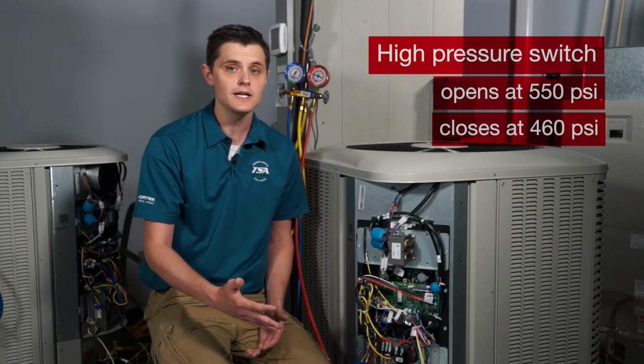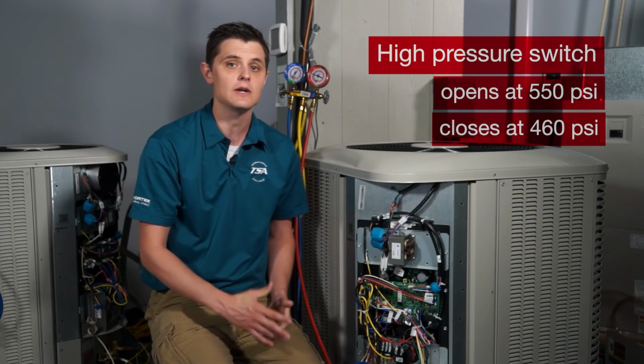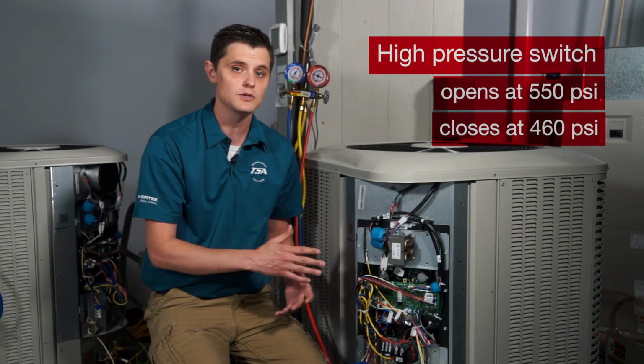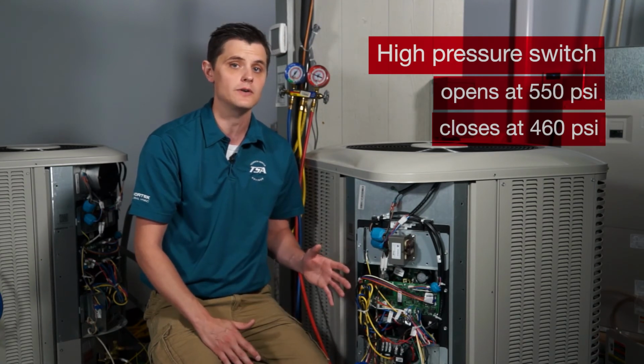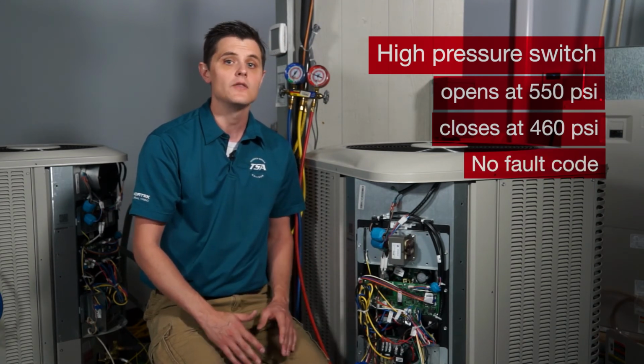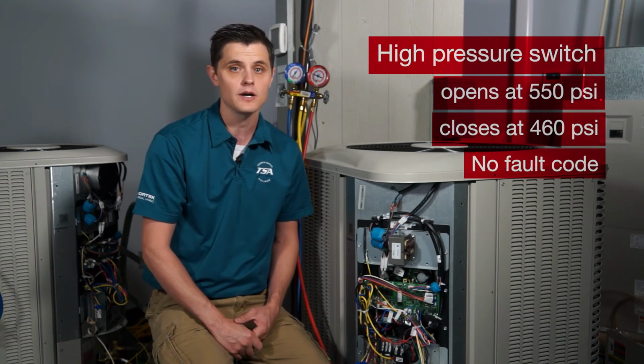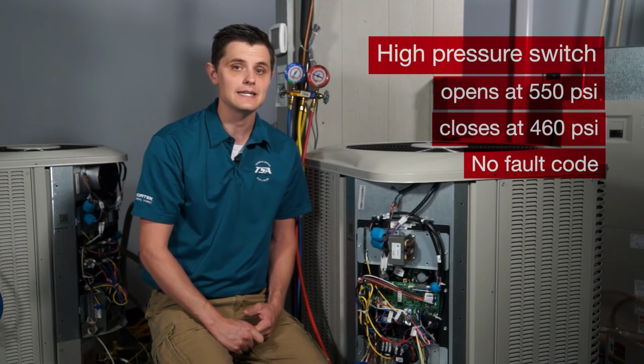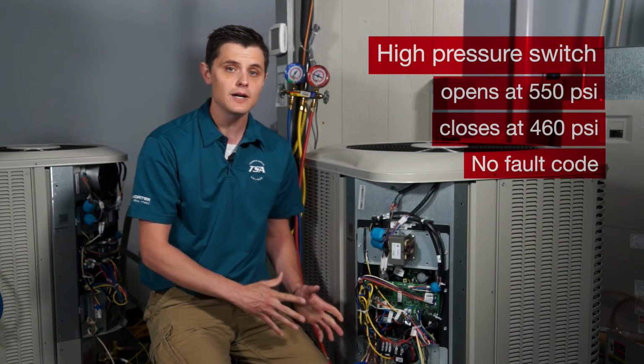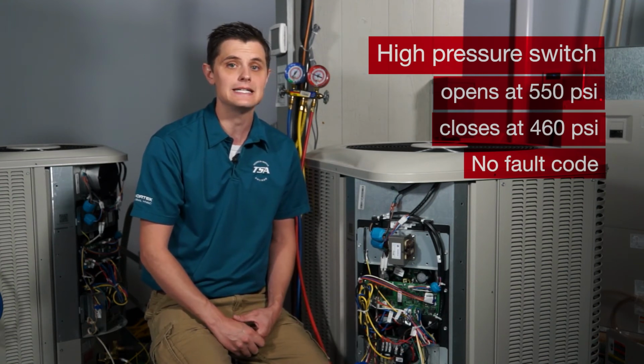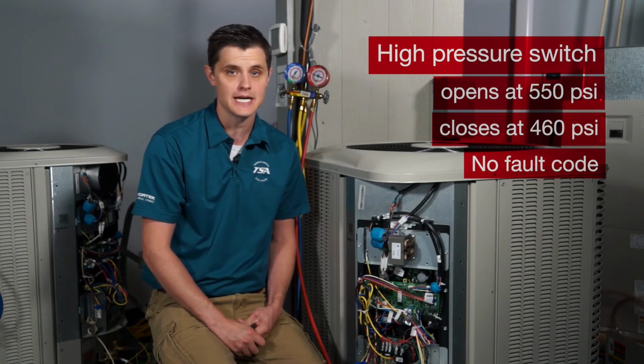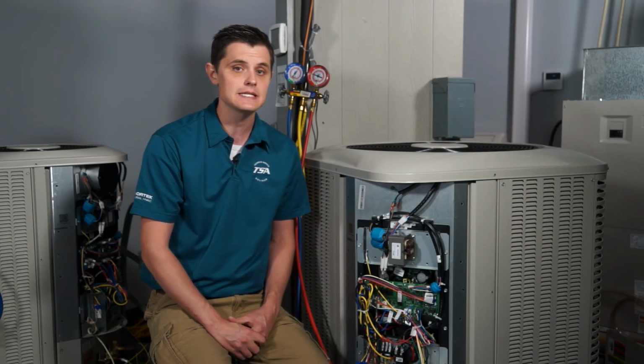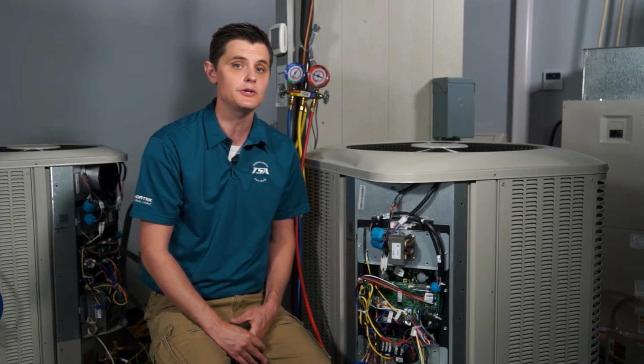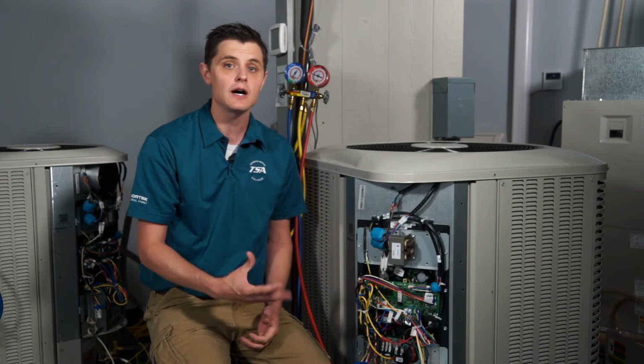Now, a side note that I want to let you guys know is that if the high pressure switch were to open on our inverter driven line units, there is no fault code that will come up for the high pressure switch. The reason for that is that the high pressure switch wiring on the low voltage side is in series with the contactor. So what'll happen is that, for example, if your high pressure switch were to open, the contactor is going to open, it's going to shut the unit down.